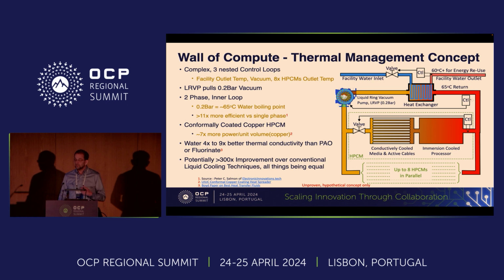And then the water passes up to the top of the module into what we call a mini immersion cooled chamber to cool the kilowatt processor. We want to eject 65 degrees C or thereabouts from every module for energy reuse purposes. So we have a control loop to control the flow depending on the power being burnt in each individual module. We then step and repeat that 8 times, because in a column in the wall of compute we have 8 modules. And then we have a heat exchanger at the top of that column to take us to the facility water. And again, we have a similar control loop on the facility water to get the higher temperature out of the facility water.